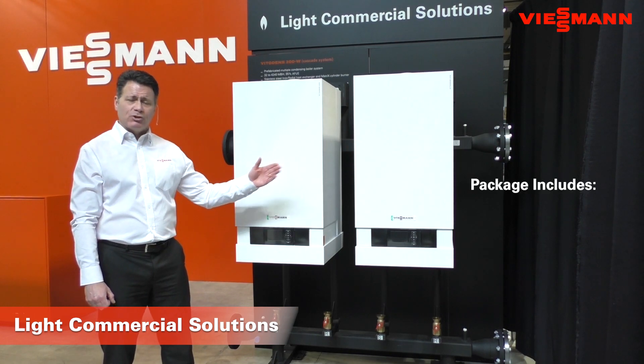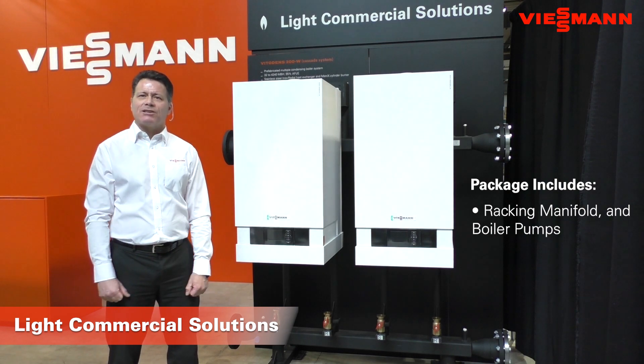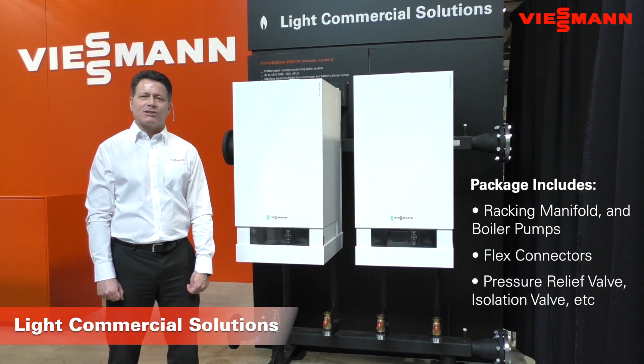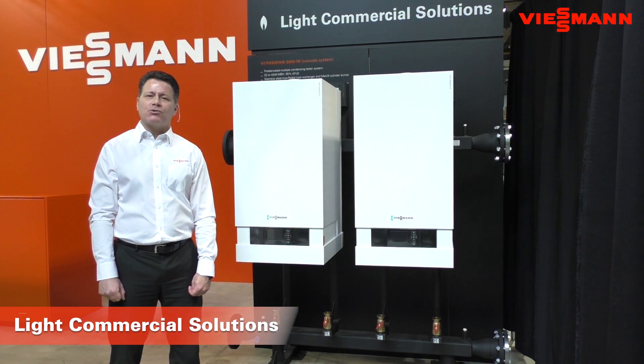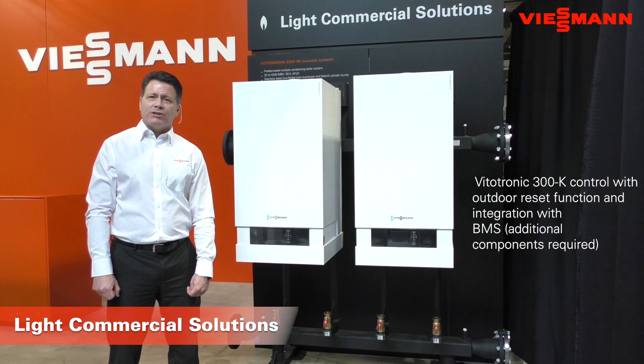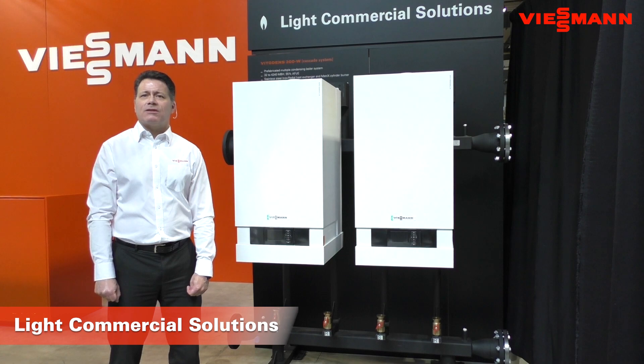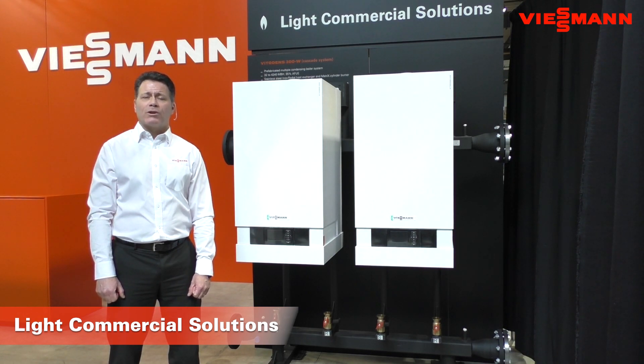The package consists of two to eight boilers, the racking manifold, boiler pumps, and all the required installation fittings including boiler pump flex connectors, pressure relief valve, isolation valves, etc. Once fully assembled, we tie it all together with our Vitotronic 300 Cascade Control — a master cascade control that will handle anywhere between two and eight boilers, outdoor reset control, multiple temperature heating systems with two mixing valves, and domestic hot water control. You can also integrate with your building automation system through hardwired points or through one of our gateways to provide BACnet or LON Works communication.